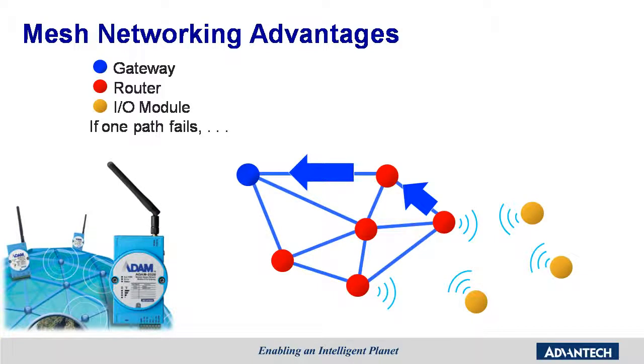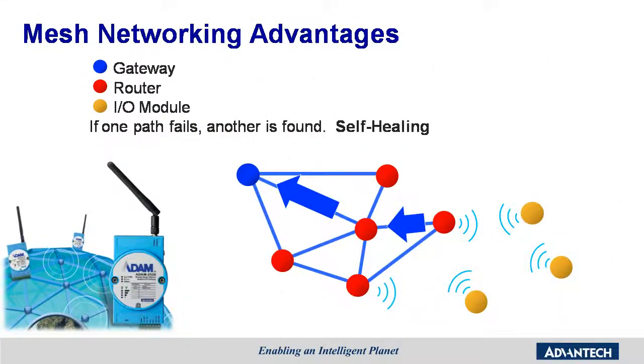With a wired or wireless networking solution, one significant concern is hardware and infrastructure failure—mainly something like a wire break, a switch failure, or the fiber optic opening up. With mesh networking, the answer is simple: the individual endpoints and nodes, or the I/O modules, are communicating with more than one point of connectivity. So with mesh, they always have a way back to the main connection. If any aspect of the connection is lost, all communication switches to the second best available path. Typically, with a single failure, no slowdown in communication is experienced at all.